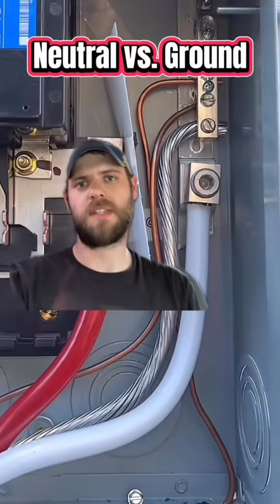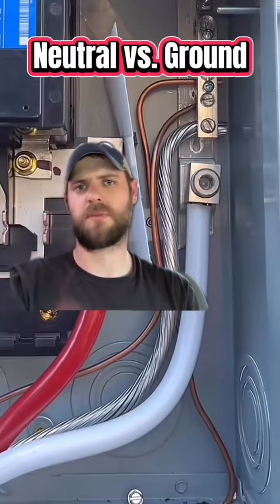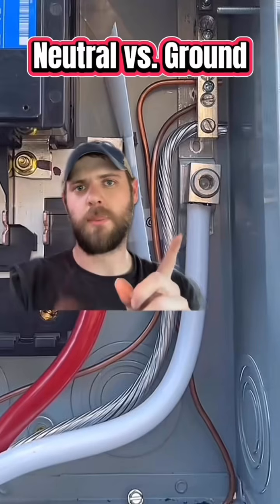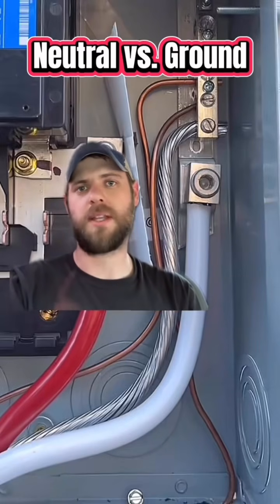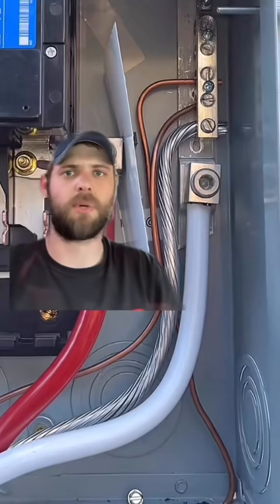So neutral and ground are the same thing since we bond them together at the service, right? Incorrect. Why do we bond neutral and equipment ground together, and why don't we bond them together anywhere else except for separately derived systems? Most of you already know the neutral is a grounded conductor. It being grounded has no effect on the purpose that it serves.